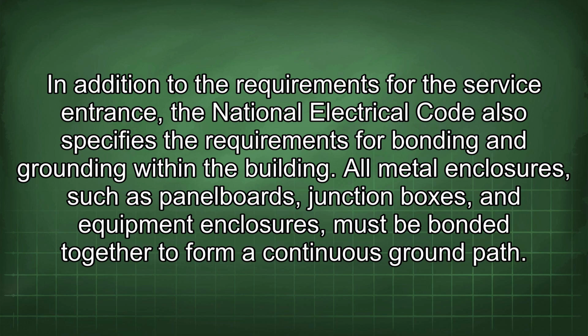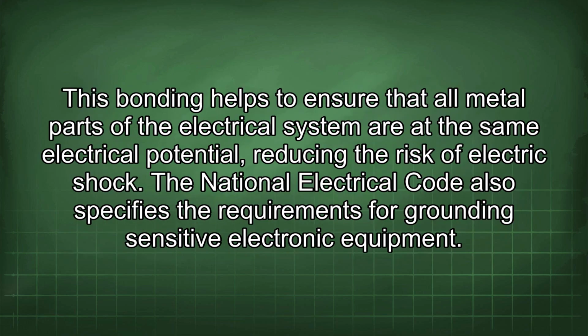In addition to the requirements for the service entrance, the National Electrical Code also specifies the requirements for bonding and grounding within the building. All metal enclosures, such as panel boards, junction boxes, and equipment enclosures, must be bonded together to form a continuous ground path. This bonding helps to ensure that all metal parts of the electrical system are at the same electrical potential, reducing the risk of electric shock.